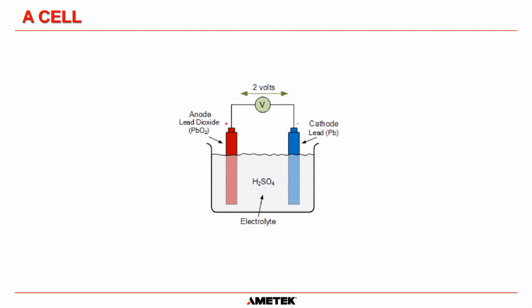If you measured the specific gravity of the electrolyte, which is a way of measuring how much acid is in the water, water is obviously a specific gravity of 1. In most circumstances, the electrolyte solution in a wet cell battery has a specific gravity of about 1.215 to 1.25. If you monitored the electrolyte as the battery discharged, you would see that the specific gravity would start to go down, because the acid within the electrolyte solution is getting absorbed into the negative plate. That is why the specific gravity goes down.